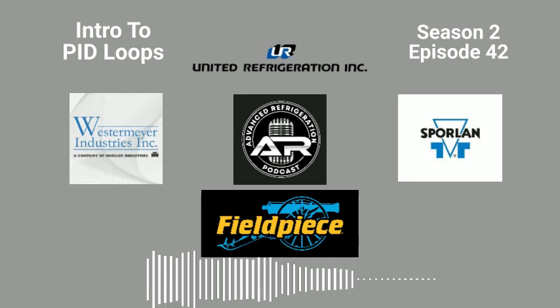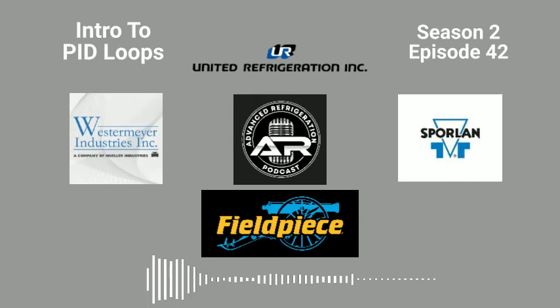They again don't use the D side. They just use the PI loop, and then that percentage. The Micro Thermo stuff and the RDM stuff is way closer to industrial PID loops than CPC. CPC is really canned down, but when you get into Micro Thermo, their loop stuff and RDM, those are true PID loops. I mean, what you could do with some of those, and setting the base values. And then go ahead, Brett.